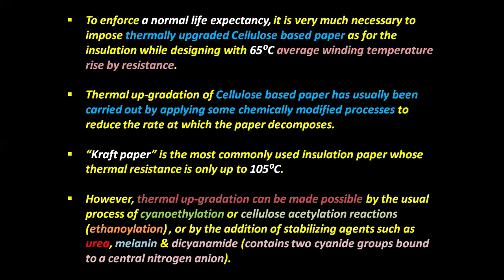Kraft paper is the most commonly used insulation paper, whose thermal resistance is only up to 105 degrees centigrade. However, thermal upgradation can be made possible by the usual process of cyanoethylation or cellulose acetylation reactions, or by the addition of stabilizing agents such as urea, melamine, and dicyandiamide, which contains two cyanide groups bound to a central nitrogen anion.